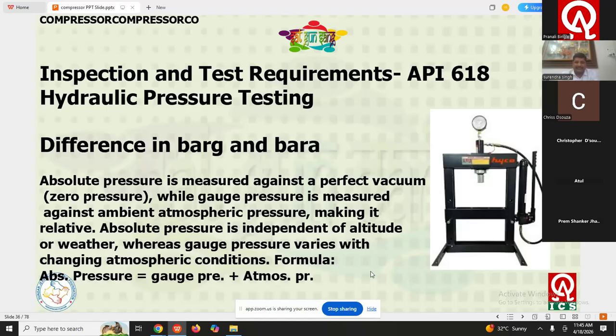There are three terminologies in pressure: absolute pressure, gauge pressure, and atmospheric pressure. Absolute pressure is equal to gauge pressure plus atmospheric pressure. So whenever the QAP states bar G, you will understand that this is bar gauge pressure. We have to understand the difference between bar G and bar A. When we see bar A, it means atmospheric pressure is also added to the gauge pressure, which comes to the absolute pressure.